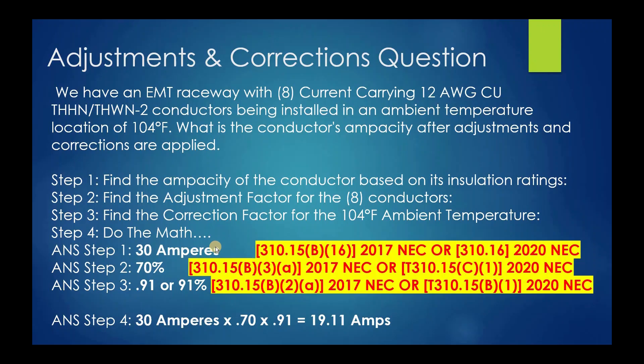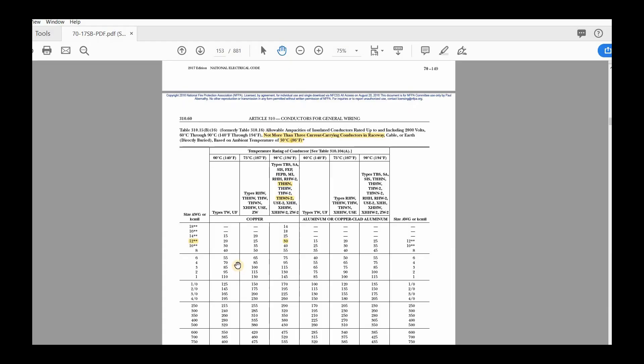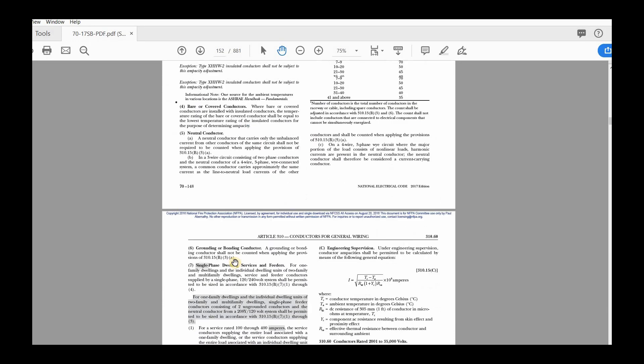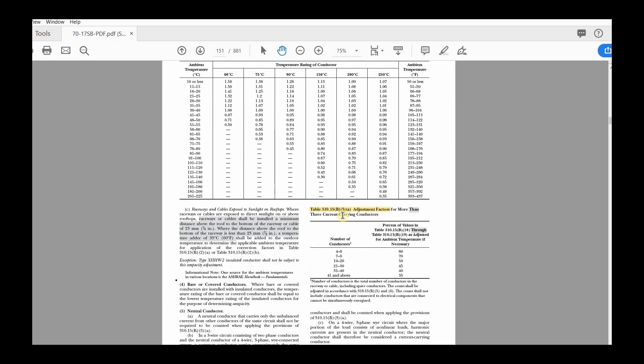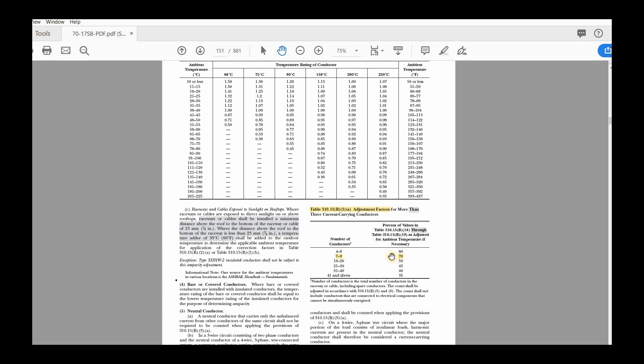So we're looking for the adjustment factor for these eight current-carrying conductors. We go back in the code to table 310.15(B)(3)(a). Here are our adjustment factors. We have four to six, seven to nine, ten to twenty, and twenty-one to thirty. Since we're dealing with eight conductors, we fall in the seven to nine range and we use 70%. Remember, we convert this to a decimal by moving the decimal two places left, so it's 0.70.